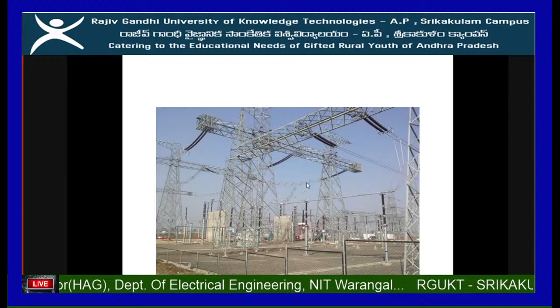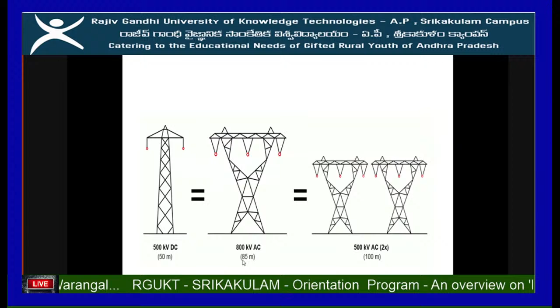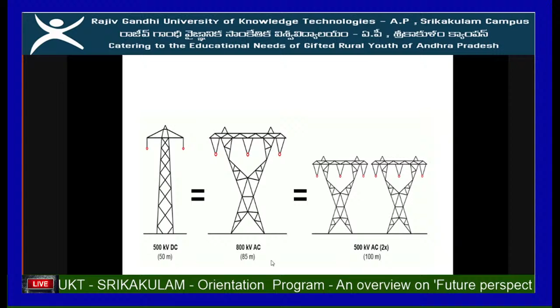So why would people go for this? DC lines are going to be very slim and equal to 800 kV, but the problem is you don't get a big corridor. If I ask for 1500 kilometers at 85 meters width, no government can really support that. Therefore they are trying to go for HVDC.